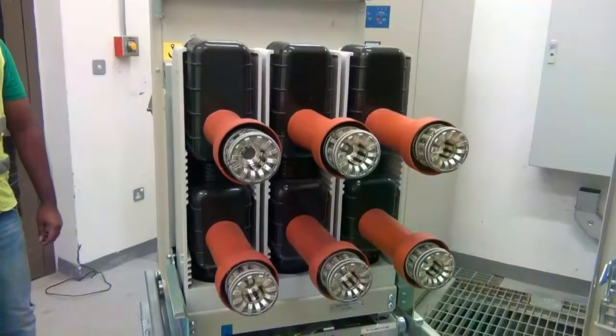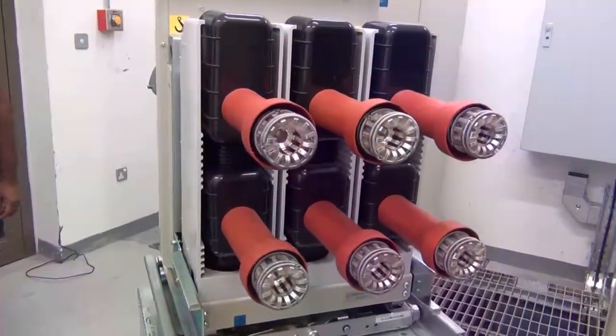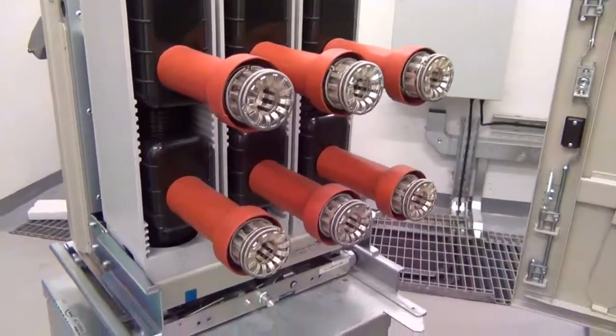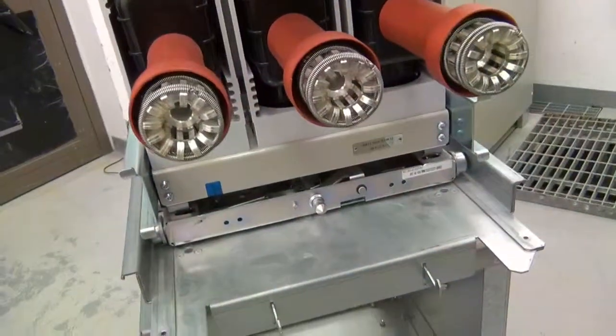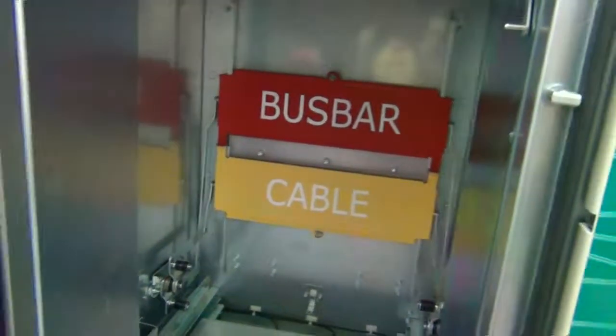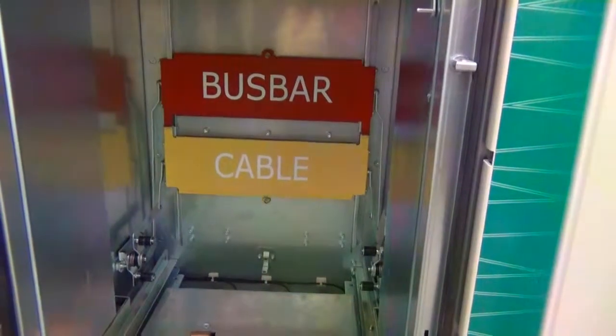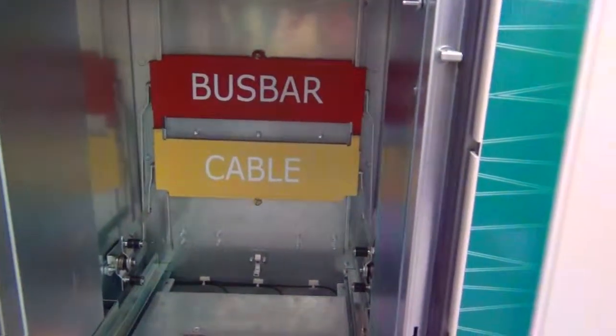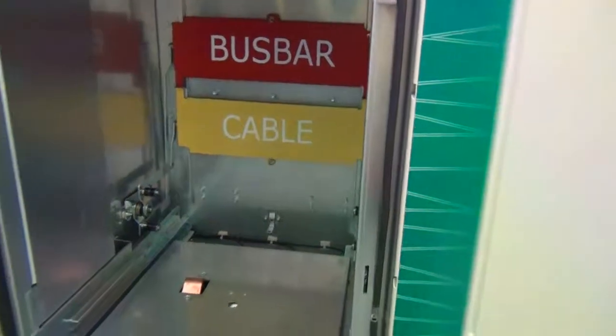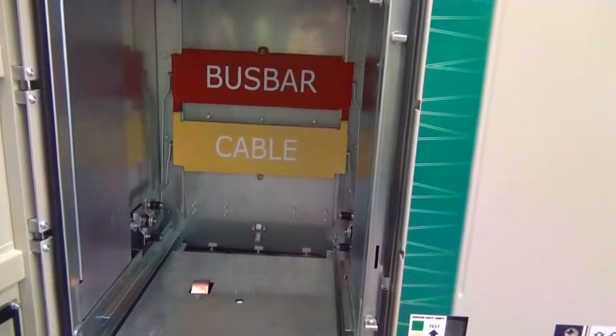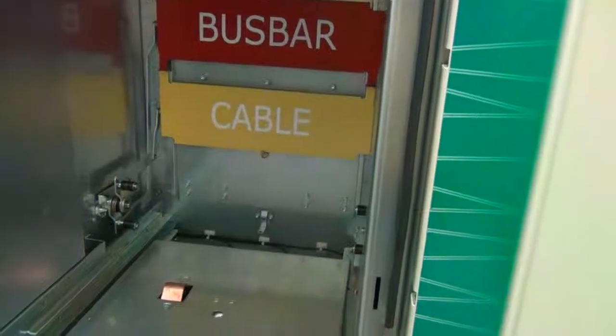The vacuum bottles are completely insulated. As you can see, the bus bars everywhere are insulated. The magnetic actuator is behind. You can also see the circuit breaker compartment with shutters. Now, in order to access the shutter, one can have a padlocking of the shutters, wherein this is the padlock which is being provided, a padlocking arrangement, so that nobody accesses it by accident.